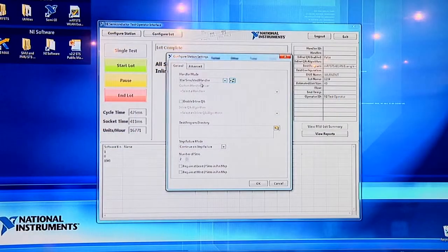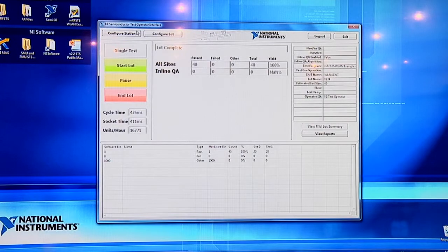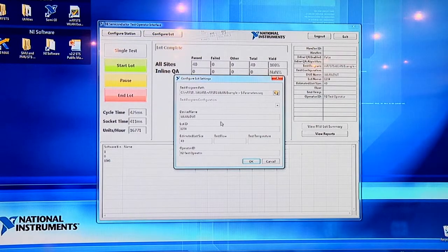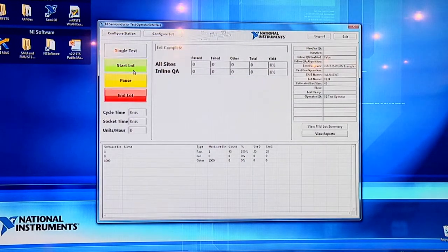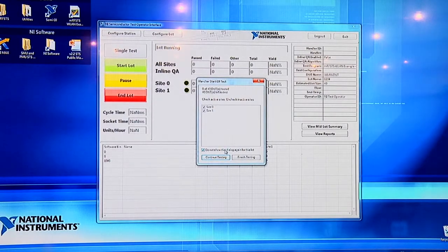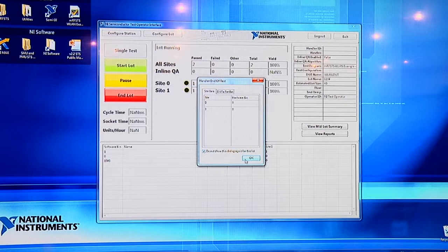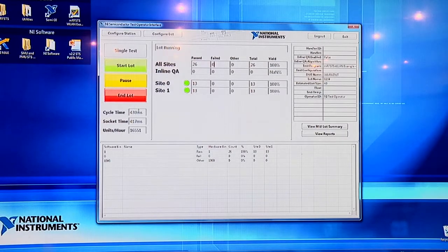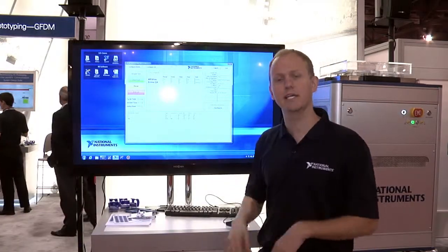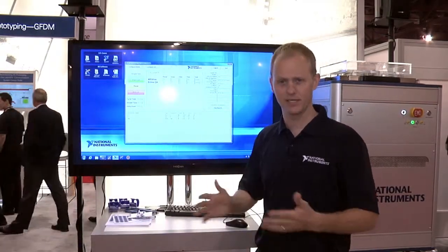We're going to use a simulated handler, configure it for 40 devices, and set this up for WLAN device test — the program we wrote in TestStand. Once we start the lot, you can see things like yield, pass, fail, and binning, as well as passing and failing rates and test time. Here we're testing about two devices every 480 milliseconds, which is quite fast. Once the run is complete, it produces a report file on disk and the test lot is complete.